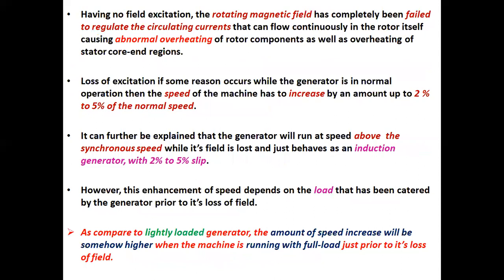With no field excitation, the rotating magnetic field has completely failed to regulate the circulating currents that can flow continuously in the rotor itself, causing abnormal overheating of rotor components as well as overheating of stator core end regions. If loss of excitation occurs while the generator is in normal operation, the speed of the machine has to increase by an amount up to 2% to 5% of the normal speed. The generator will run at speed above the synchronous speed while its field is lost, and just behaves as an induction generator with 2% to 5% slip.